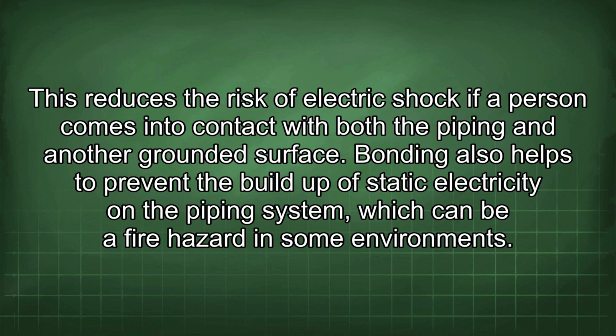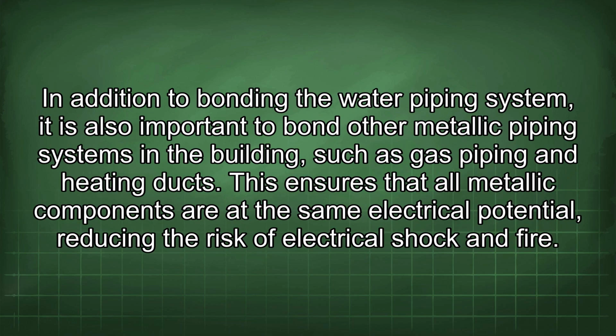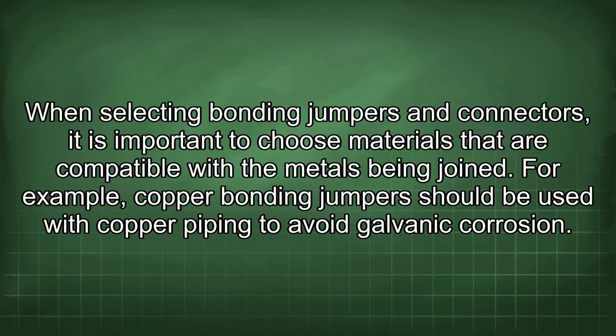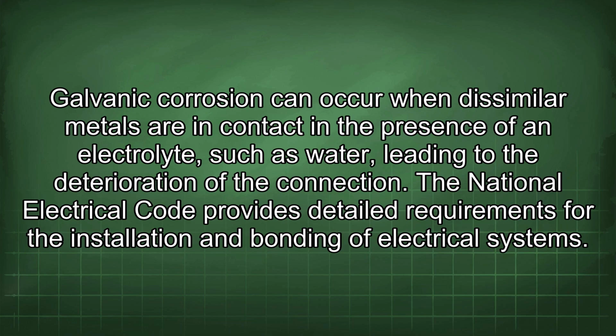In addition to bonding the water piping system, it is also important to bond other metallic piping systems in the building, such as gas piping and heating ducts. This ensures that all metallic components are at the same electrical potential, reducing the risk of electrical shock and fire. When selecting bonding jumpers and connectors, it is important to choose materials that are compatible with the metals being joined. For example, copper bonding jumpers should be used with copper piping to avoid galvanic corrosion. Galvanic corrosion can occur when dissimilar metals are in contact in the presence of an electrolyte, such as water, leading to the deterioration of the connection.